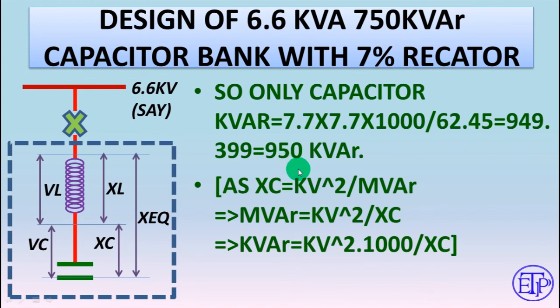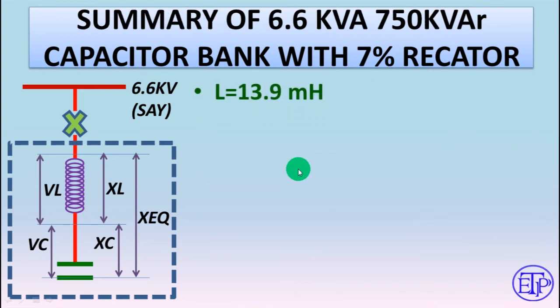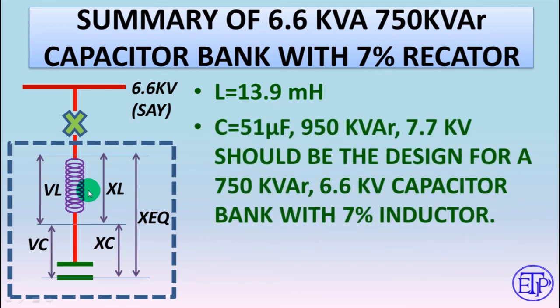The summary of the design: inductance = 13.9 mH, capacitance = 51 microfarads, 950 KVAR at 7.7 kV. This is the complete design for a 750 KVAR, 6.6 kV capacitor bank with a 7% inductor. When sizing a capacitor bank, first check the power factor improvement required to find the KVAR rating of the entire capacitor-reactor bank, then select the individual component ratings using this formula.